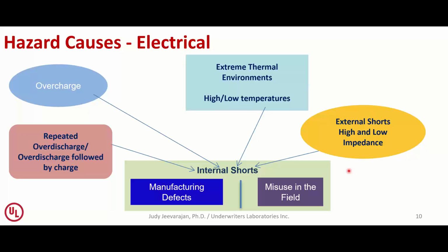Internal shorts can be caused in two different ways: manufacturing defects, and misuse in the field. Manufacturing defects are more subtle and difficult, and can manifest as larger internal short circuits in the field during use. Misuse in the field is anytime you do not design your battery properly to address these other hazard causes, leading to the generation of an internal short inside your cell or battery, which can cause a failure.